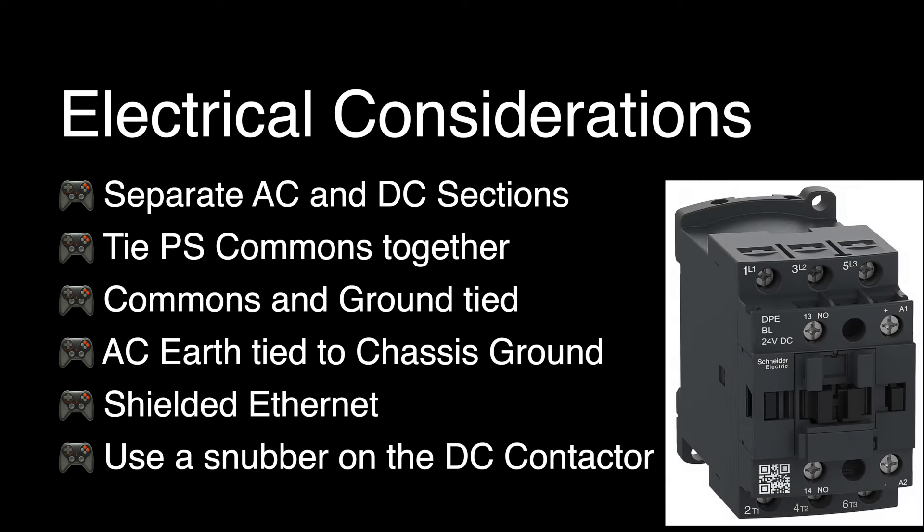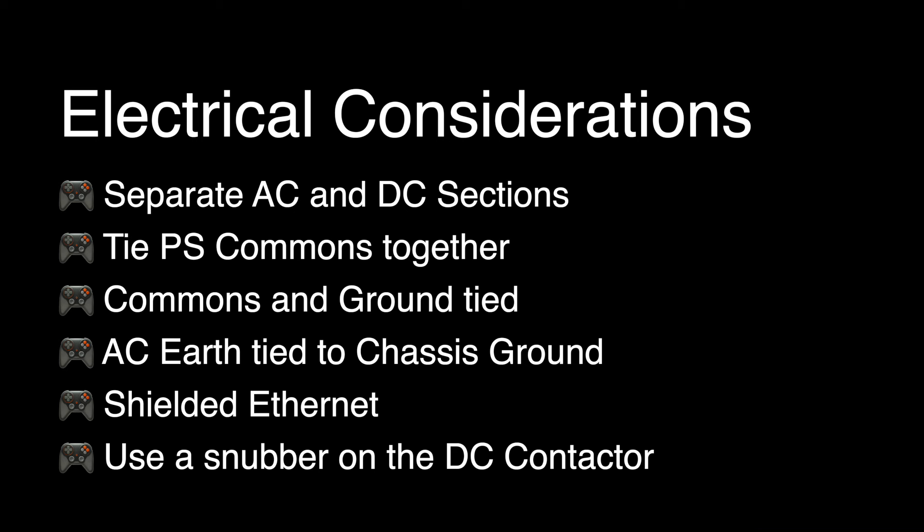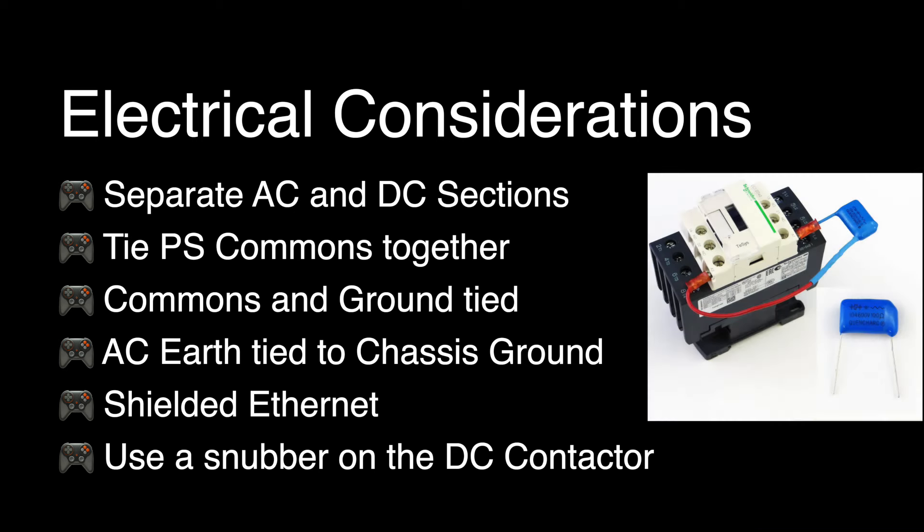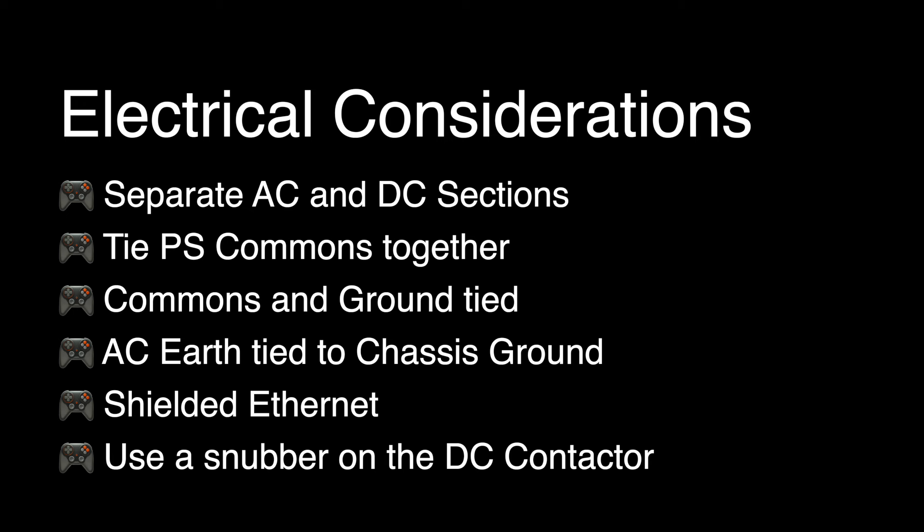A DC contactor allows rapid control of power to the motors. A snubber is required on the contactor to eliminate inductive kickback in the circuits when the contactor operates.